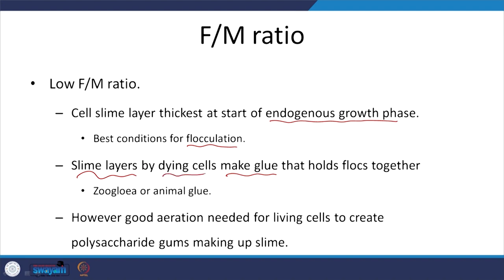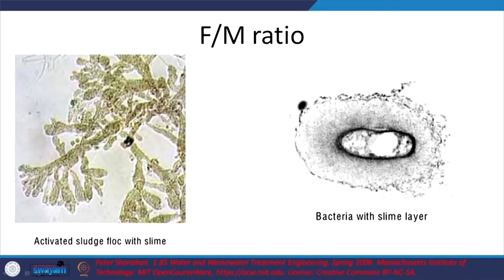Slime layers are formed when we have dying cells. To get this slime layer we need good aeration for the living cells to create the relevant polysaccharides that make up the slime. So to achieve conditions that lead to formation of this gluey or sticky layer, you need to aerate well. Here we have bacteria with the relevant slimy layer around them — activated sludge flocs with slime — which is what we get when we maintain F/M at the sweet spot.